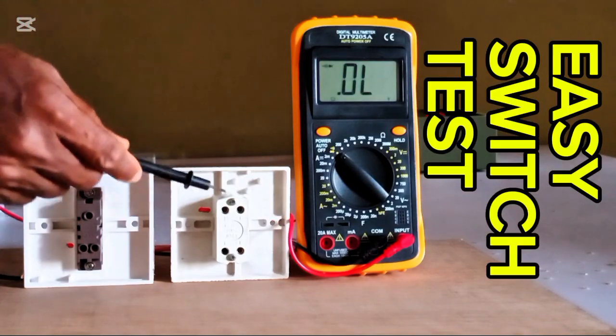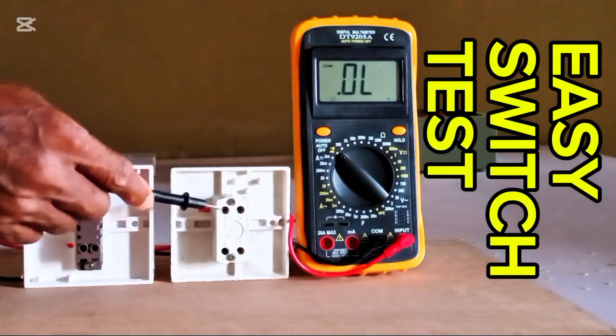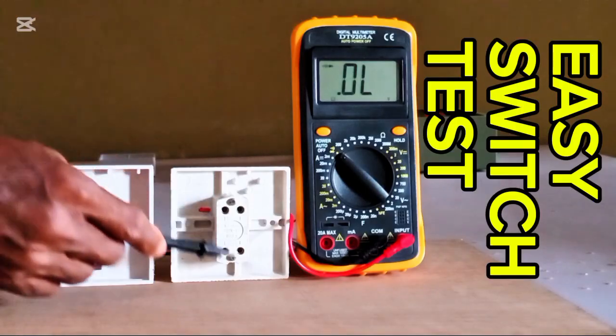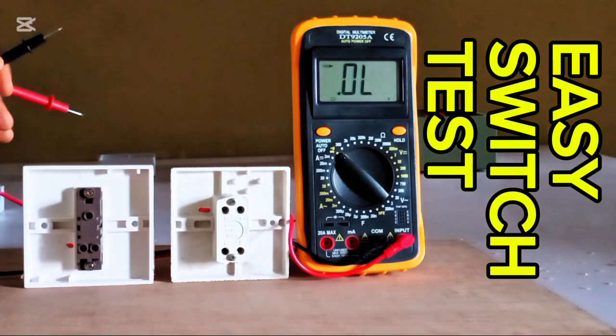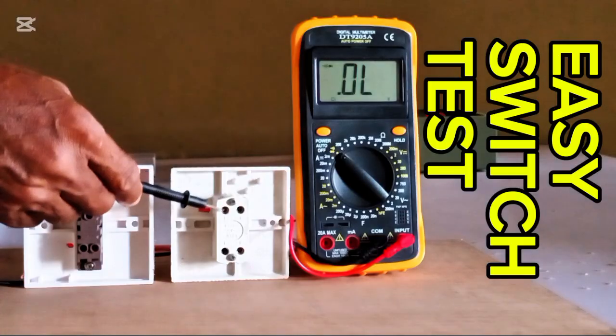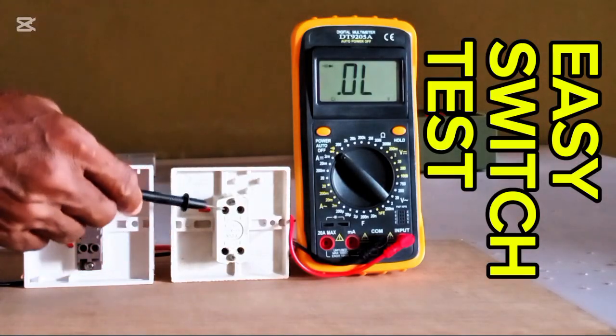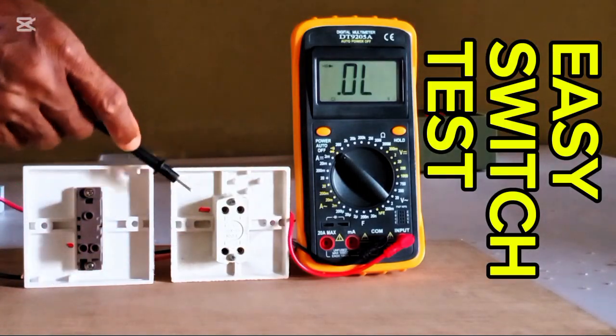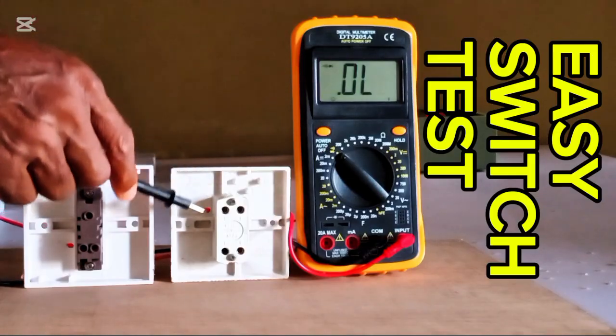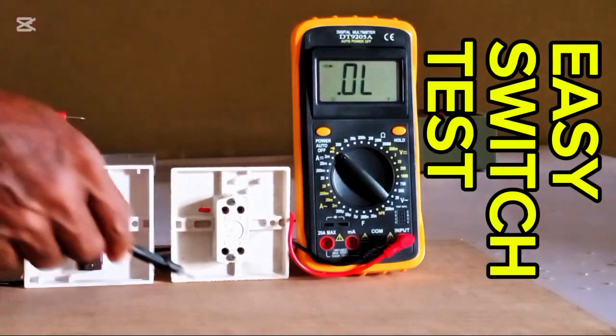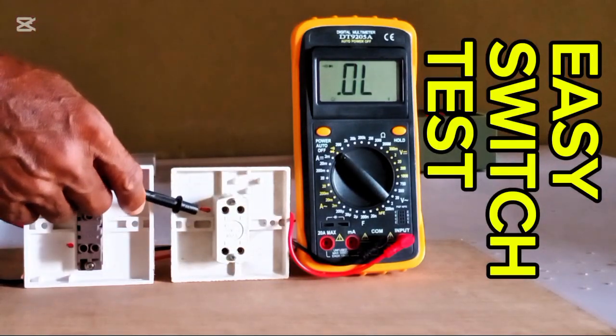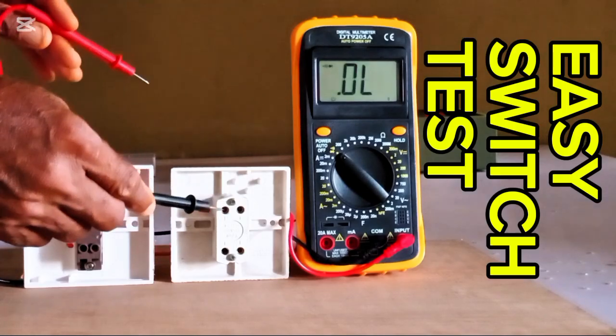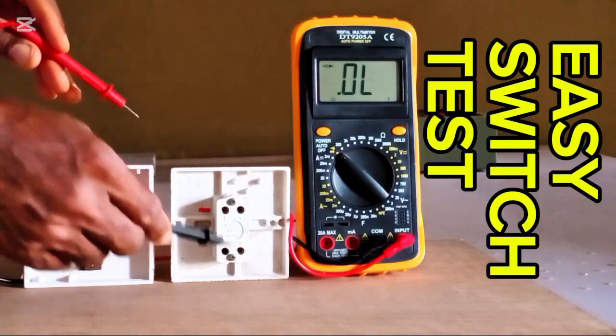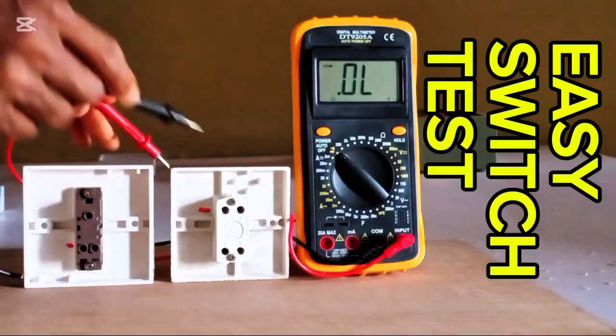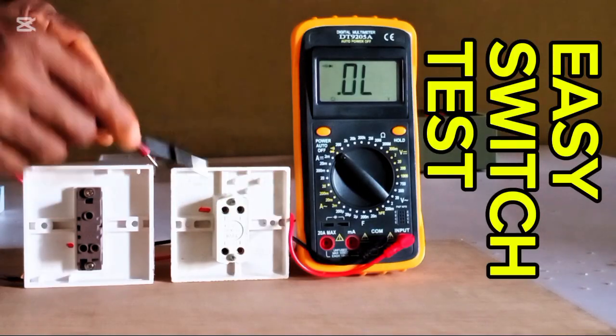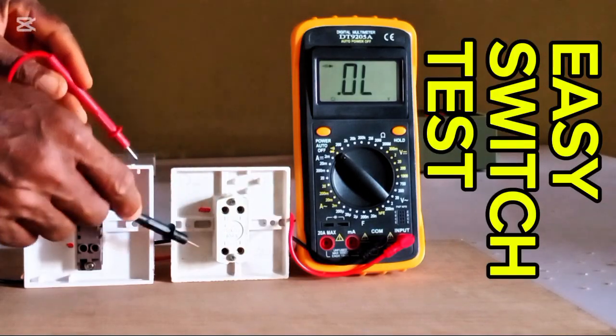Now, in each flip, either horizontal or vertical or diagonal makes in one flip. Should the diagonal and vertical make in one flip, it means the intermediate switch internally, the bars have been bridged and so will not be useful. Now, if the diagonal is meant to read and it fails to read in another flip, then it means internally it is open.